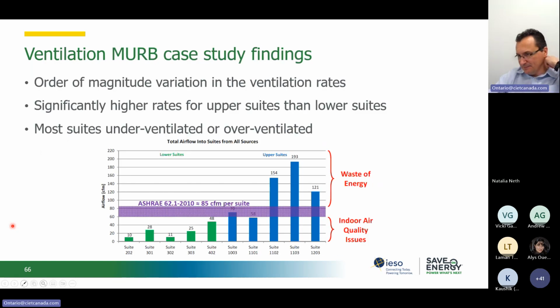Looking at some of the findings shared by that project. We see what the recommendation is for ASHRAE 62.1 in terms of ventilation, so fresh air provided to the space. We see that as we move up, we had more than required, so that presented an opportunity for improving efficiency because that air is not required. But you also notice that we had a problem with the lower floors where we did not provide the amount of fresh air required in this case.